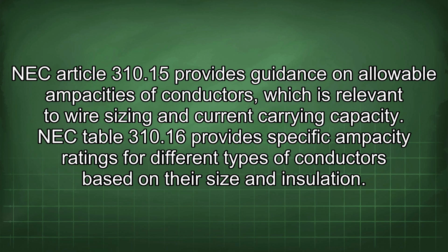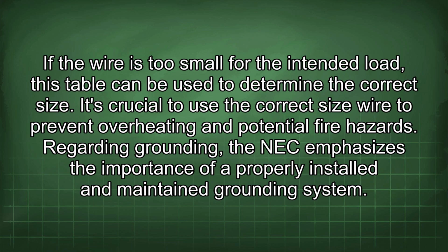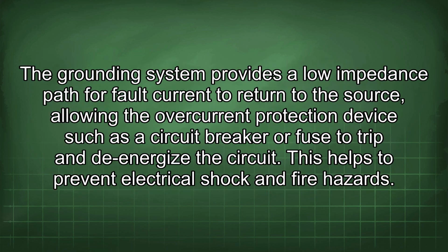NEC Table 310.16 provides specific ampacity ratings for different types of conductors based on their size and insulation. If the wire is too small for the intended load, this table can be used to determine the correct size. It's crucial to use the correct size wire to prevent overheating and potential fire hazards. Regarding grounding, the NEC emphasizes the importance of a properly installed and maintained grounding system. The grounding system provides a low impedance path for fault current to return to the source, allowing the overcurrent protection device such as a circuit breaker or fuse to trip and de-energize the circuit. This helps to prevent electrical shock and fire hazards.